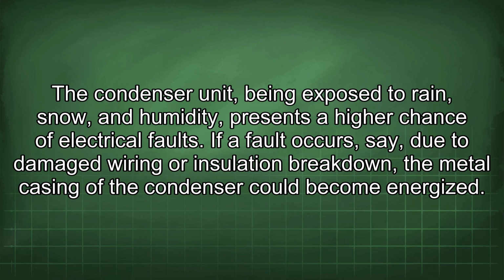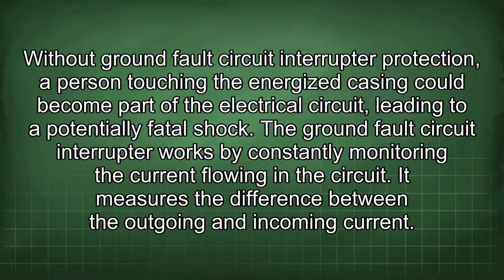If a fault occurs, say, due to damaged wiring or insulation breakdown, the metal casing of the condenser could become energized. Without ground fault circuit interrupter protection, a person touching the energized casing could become part of the electrical circuit, leading to a potentially fatal shock.